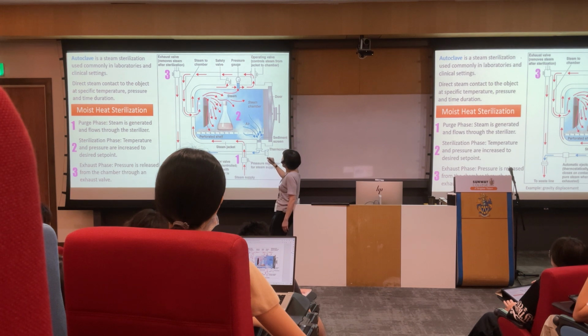When it enters, the first thing is that you push out the existing air inside the chamber, because this is the cold air, so this is not hot. You have to push it out to here, and then it will go down here. Of course the steam will turn into water and drip here. There is a bottle to collect the water. And as it keeps pushing, the chamber will fill up with very hot steam. This hot steam can go up to 121 degrees Celsius.